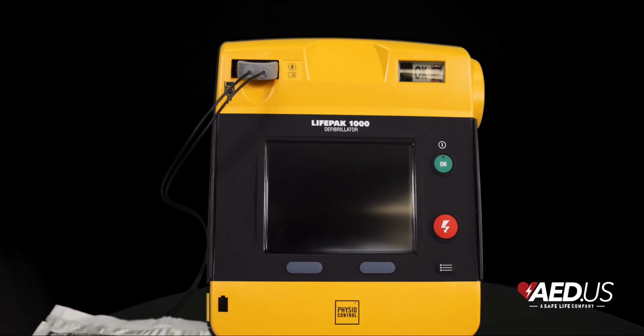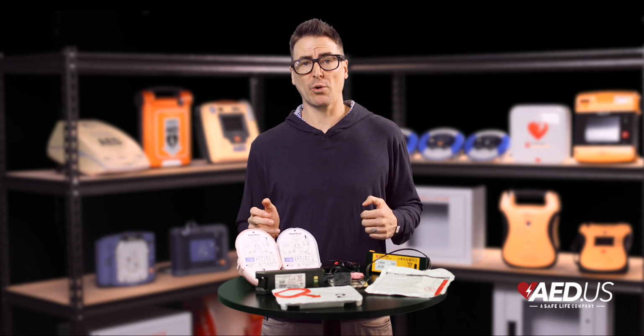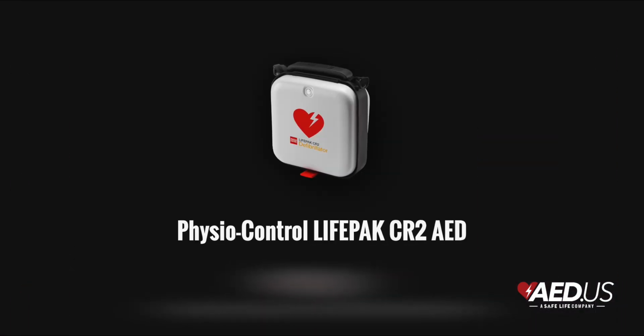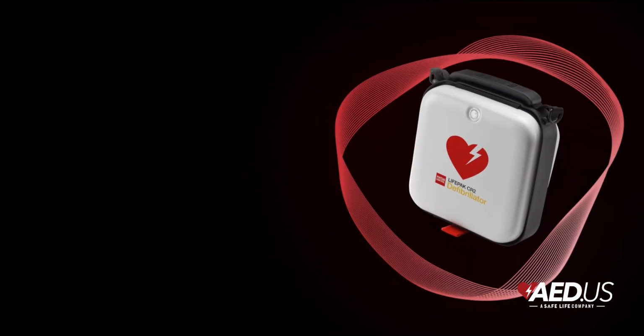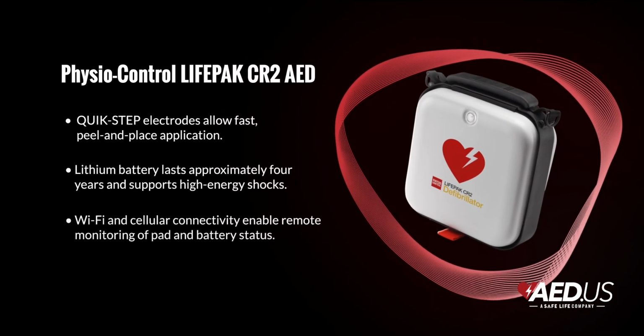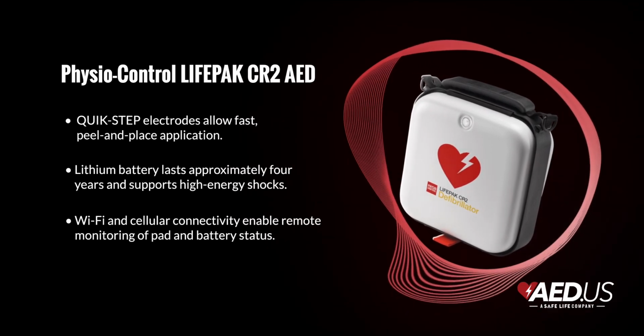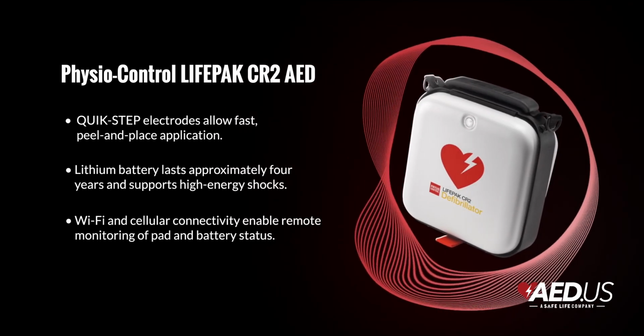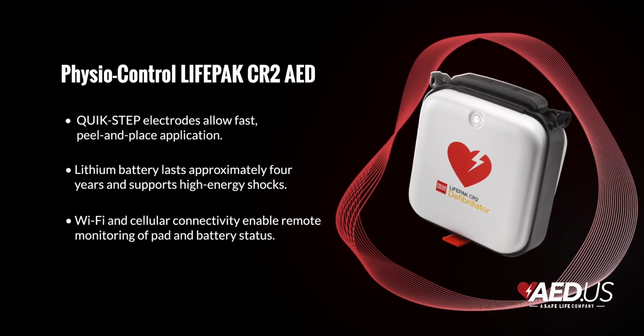The LIFEPAK CR2 uses Quick Step pads, which are pre-connected, non-polarized, and compatible with both adults and children. Switching to pediatric mode is as simple as pressing a button, making it quick and intuitive during an emergency.